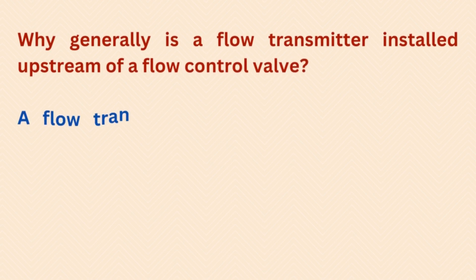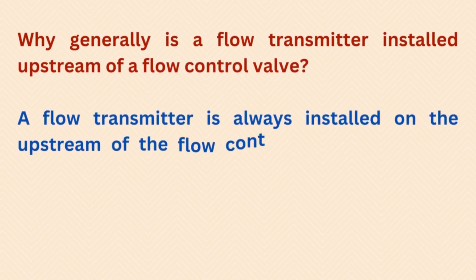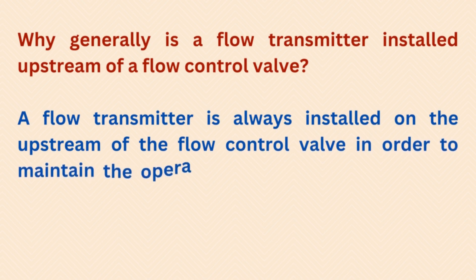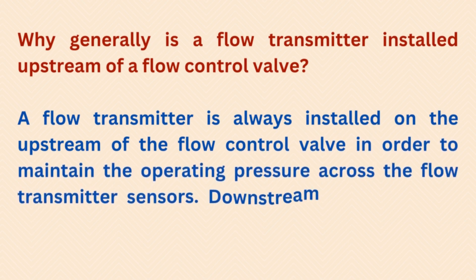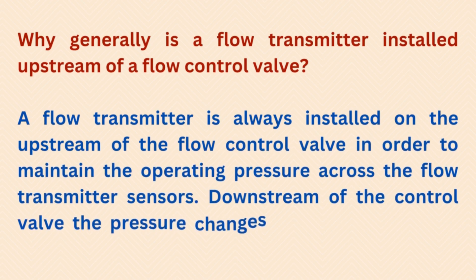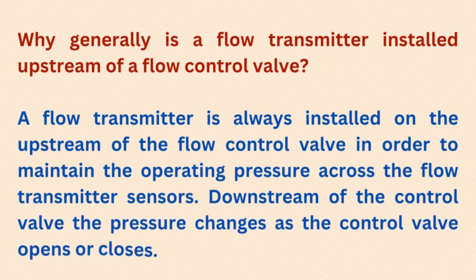Why generally is a flow transmitter installed upstream of a flow control valve? A flow transmitter is always installed on the upstream of the flow control valve in order to maintain the operating pressure across the flow transmitter sensors. Downstream of the control valve, the pressure changes as the control valve opens or closes.